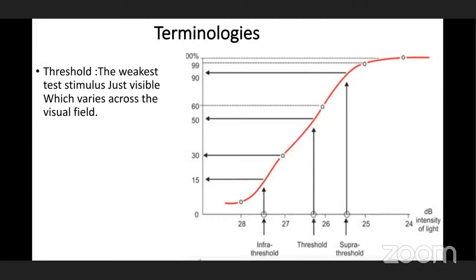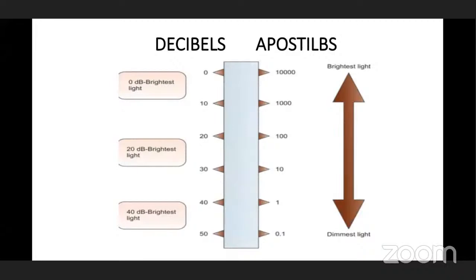Next, we have decibels and apostilbs. Decibels are a relative unit — the value used in HFA. Apostilb is the absolute unit, which is fixed and does not vary from instrument to instrument. 0 dB is the brightest light, equal to 10,000 apostilbs. 0 dB is inversely proportional to apostilb.